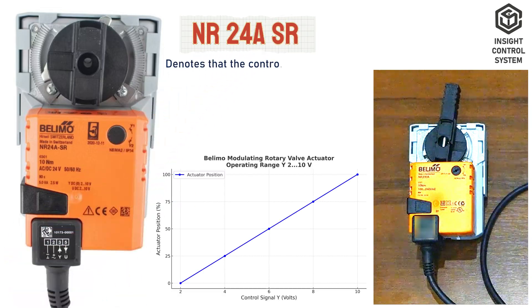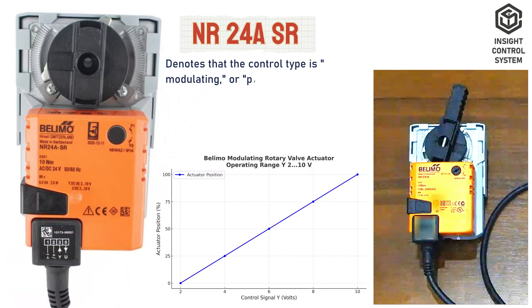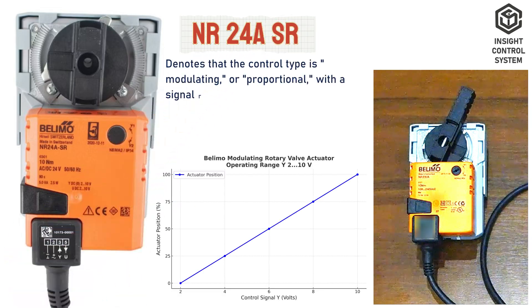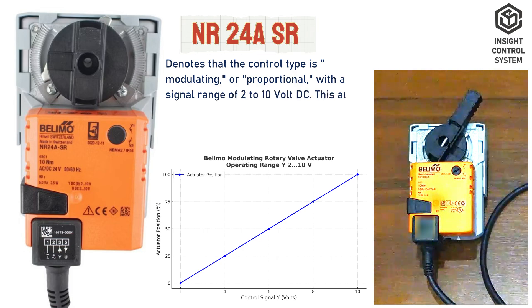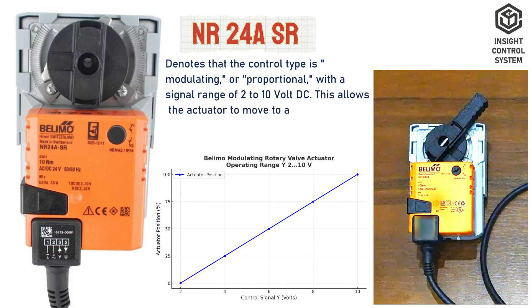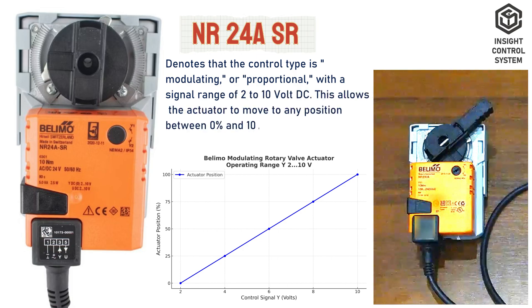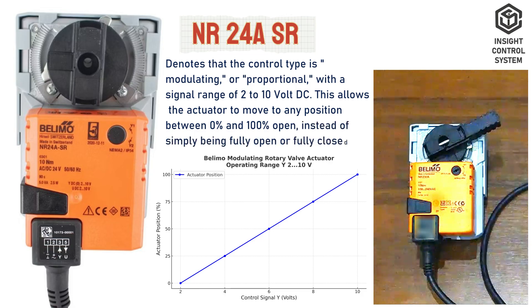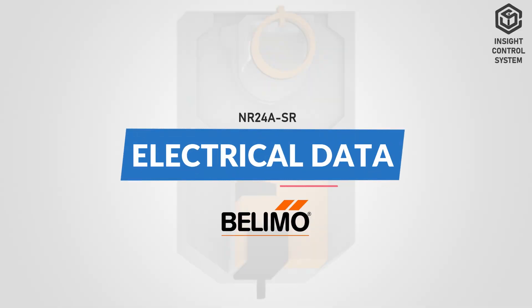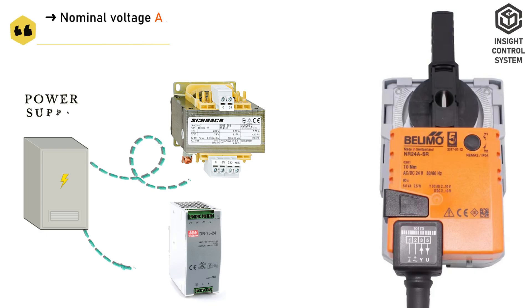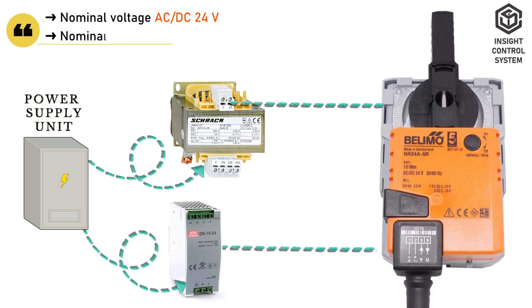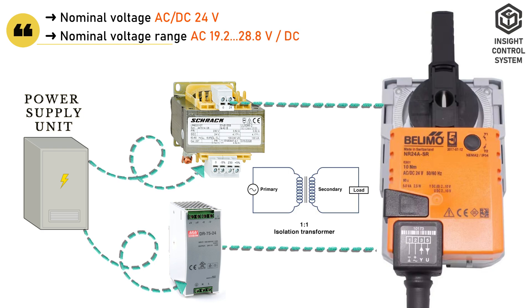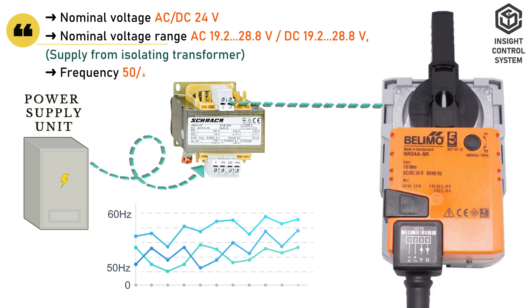SR denotes that the control type is modulating or proportional with a signal range of 2 to 10V DC. This allows the actuator to move to any position between 0% and 100% open, instead of simply being fully open or fully closed. For electrical data: voltage is AC or DC 24V, with supply from the isolating transformer. Frequency is 50 or 60 Hz.